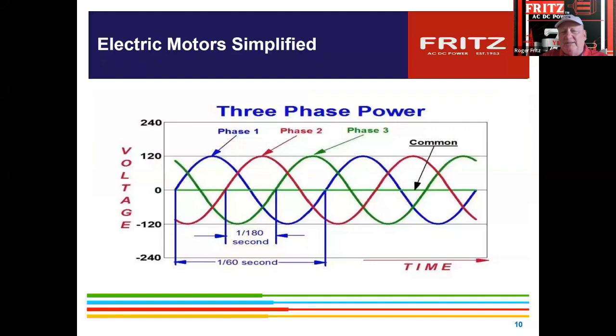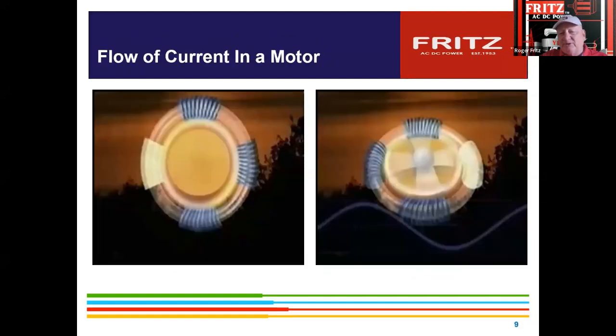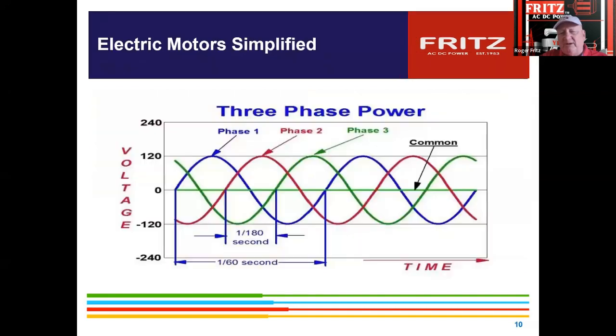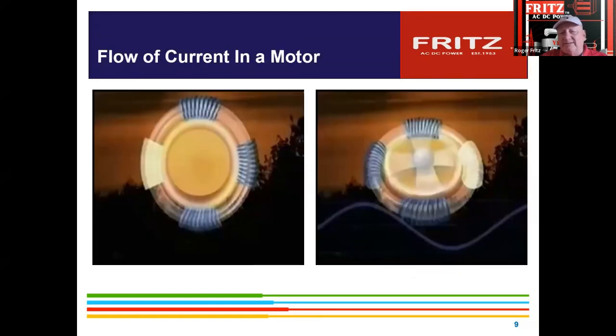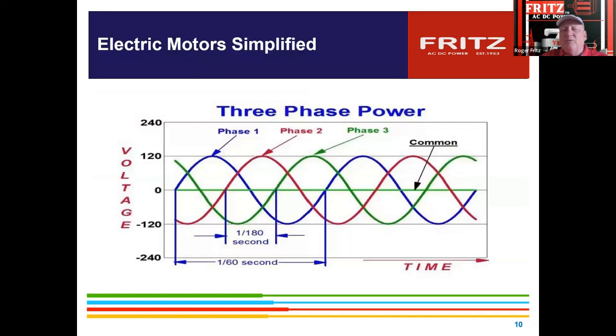But then when you do that, you get the advantage. This shows a single phase set of coils on a four pole machine, while this shows all the sine waves of three phase power, when you have three power lines feeding the motor. One other point is that you can take a single phase input and drive a full three phase variable output to the motor, because we're doing it from DC. There are savings there, because a single phase motor is about 65 to 70% efficient, and a three phase motor is up in the 90s. You normally have about a 1.5 to 2% loss in the VFD components, but the energy savings and balancing of power definitely correct for efficiency gains.